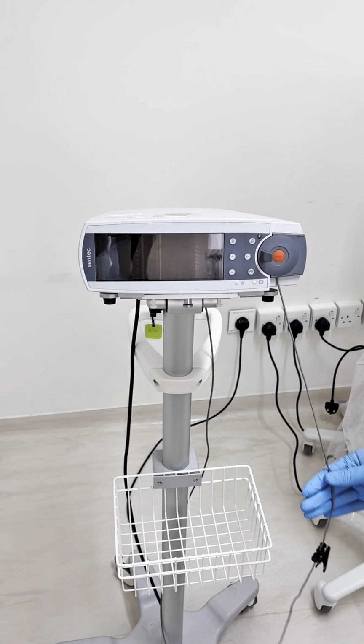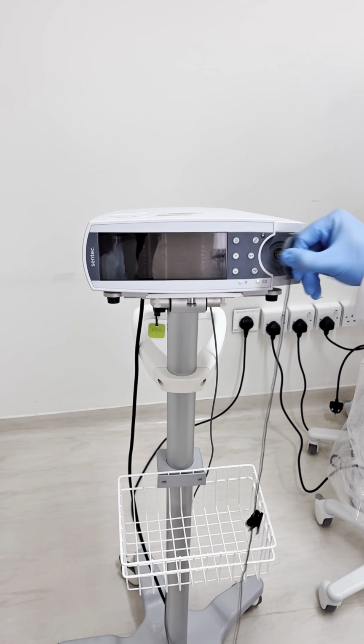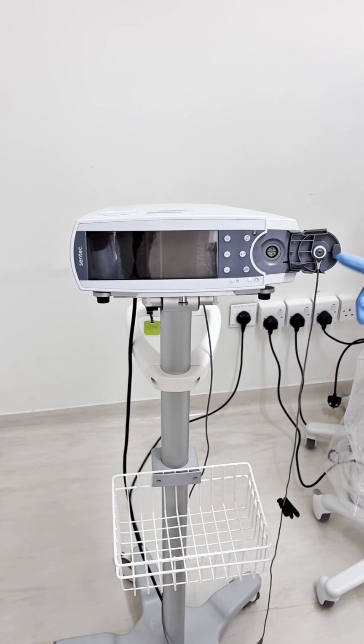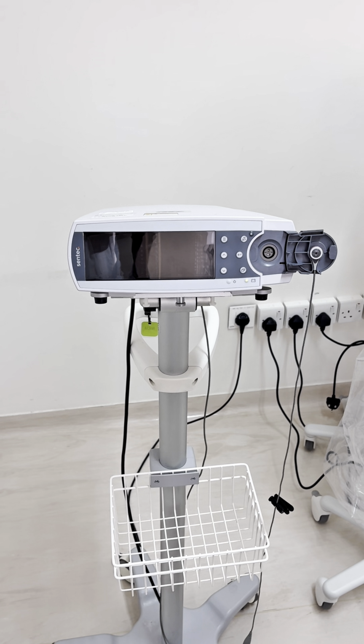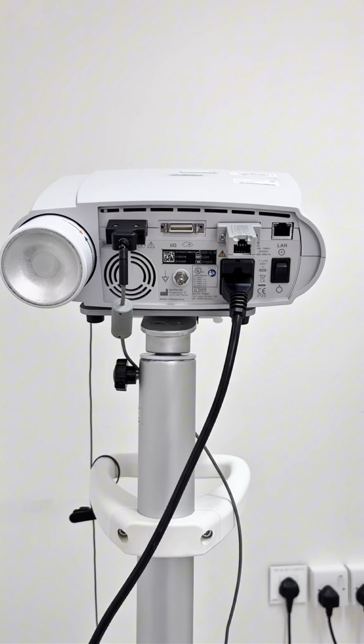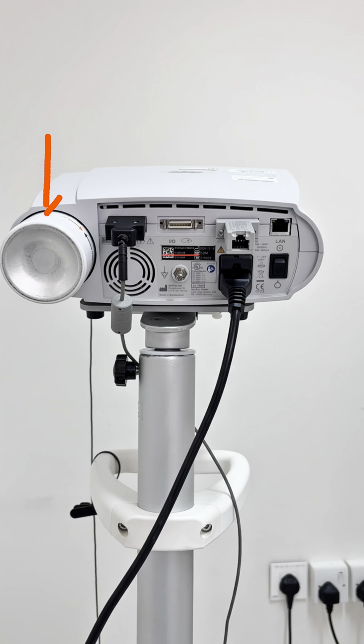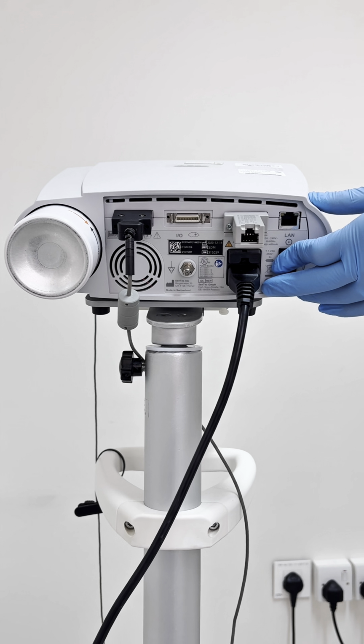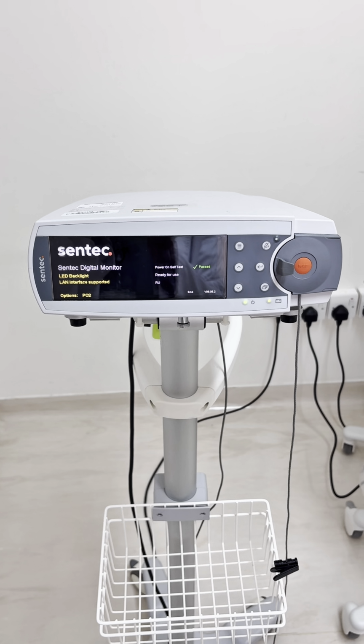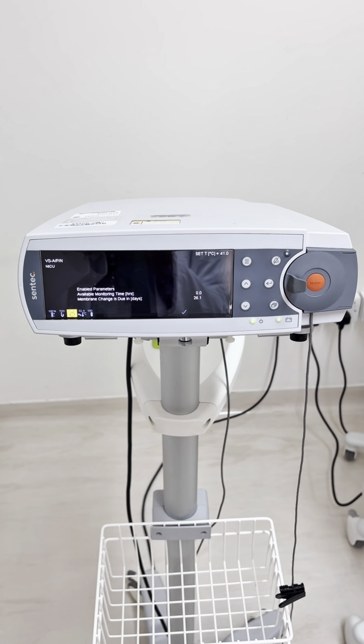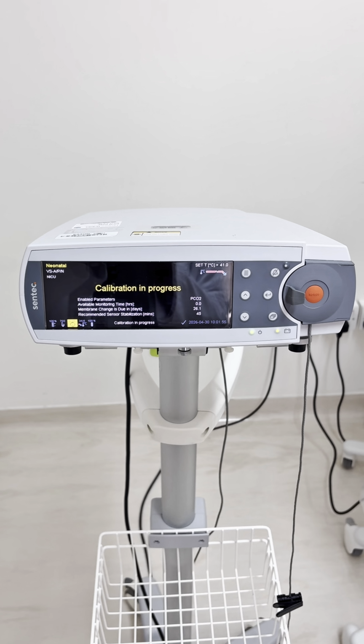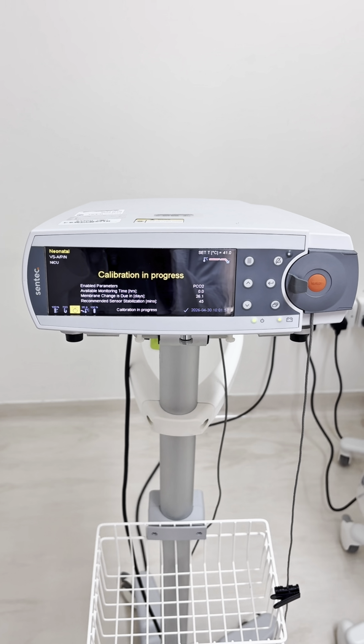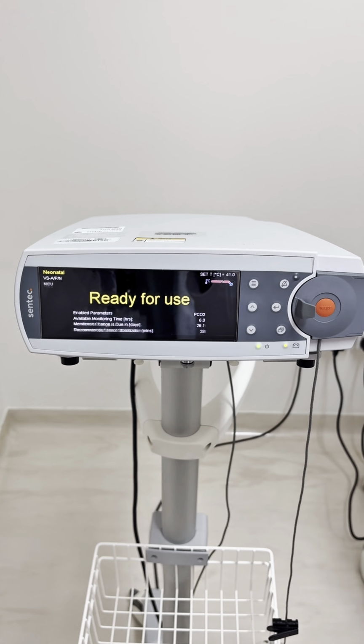Now, before turning on the device, make sure the sensor is placed inside the docking station and the cable is connected. In the back side of the device, here is the gasket for gas calibration. Here is the main sensor cable, system integration port, power cable, and the power button. After turning it on, the system will automatically do calibration for about 5 to 10 minutes until it shows the ready to use message. Now it is ready for use.